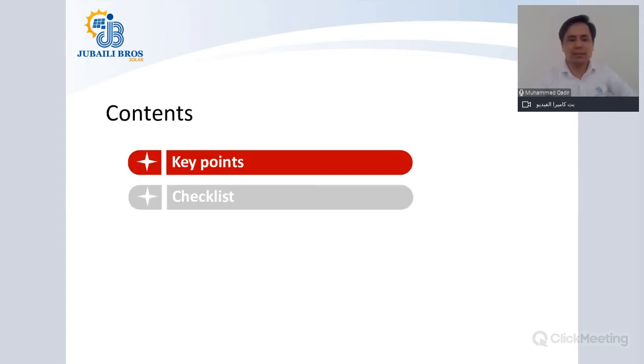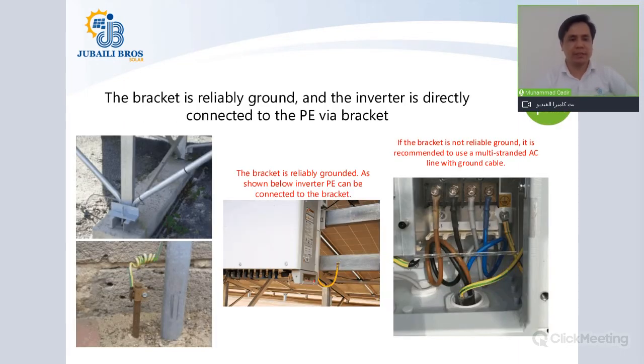So to proceed with the plant construction guideline, there are key points that need to be noticed when you are installing Huawei inverters. So we go ahead with the first slide, which is about the earthing of your inverters. Now there can be many different scenarios where you will be installing your inverters. It could be on the back of your arrays on a ground mount, it could be on a wall, or it could be on a steel plate outdoor. One thing that has to be noticed, which is being discussed here, is the bracket must be reliably grounded and the inverter is directly connected to the PE via bracket.